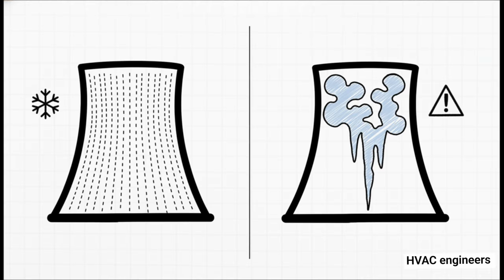Thanks to their specific nozzle cups, these towers can drop down to just 30% of their design flow and still distribute water evenly. That keeps the heat load pushed to the exposed outer edges, which totally prevents freezing.